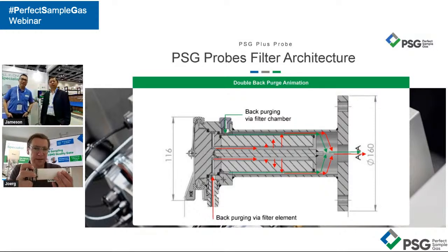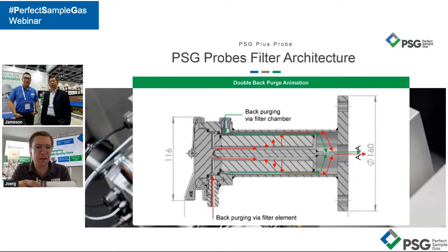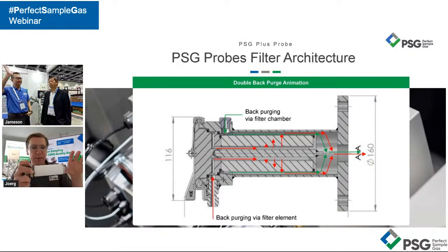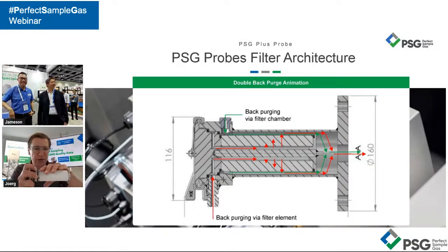So this is really the advantage of this strategy. And Jameson, this is also something you should mention. Handling back purging is an additional effort. So there has to be a sequence for the back purging. You have to bring the instrument air to the probe. And at the same time, you also have to consider that if you choose the wrong strategy for the back purging, what can happen is that the temperature inside the probe might drop.